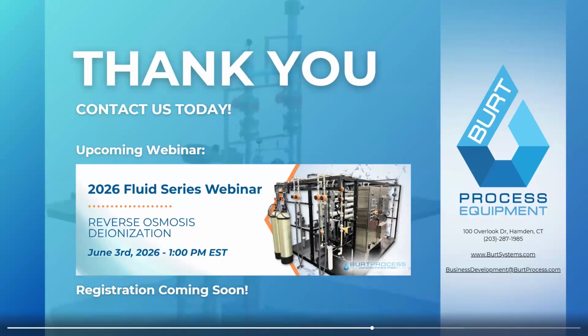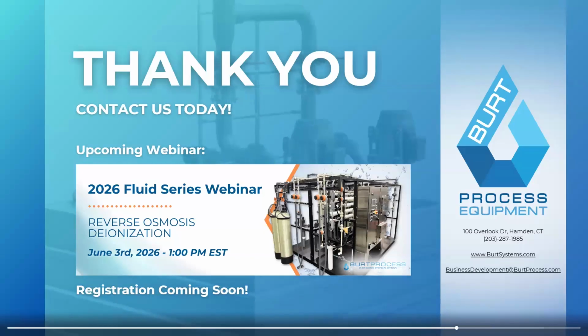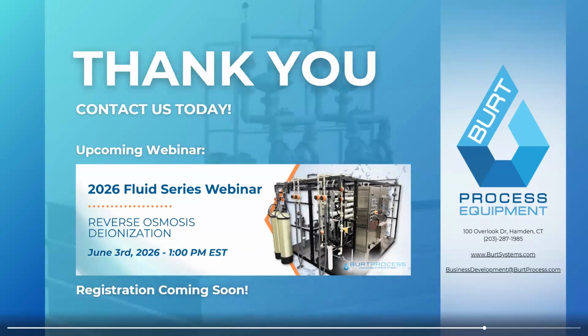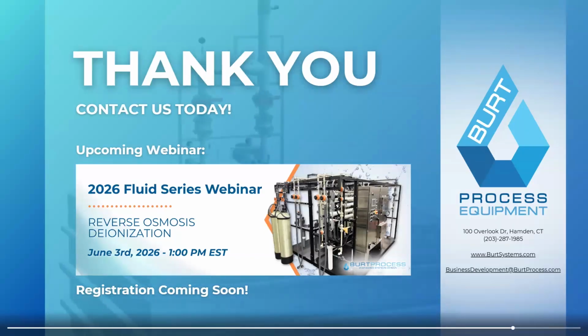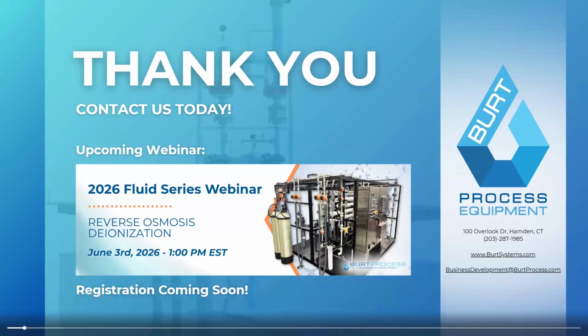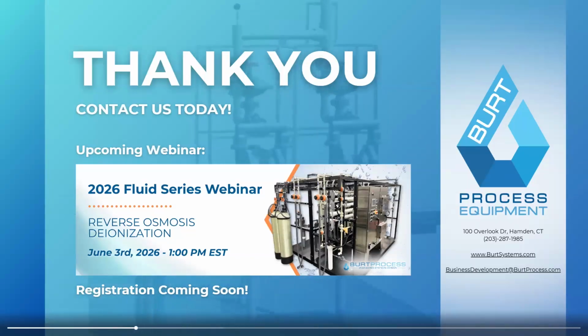The other thing I caution people about is that a lot of times, when you need a pH system for a project, you actually need it very early in the building construction, because you need to start up your WFI stills and your other processes in your building before it goes fully operational. So oftentimes, very early on in a project, before you're actually seeing the true nature of the waste, you will see that need come up, because all you're really doing is dumping WFI water down the drain as you're starting up or testing your other systems.